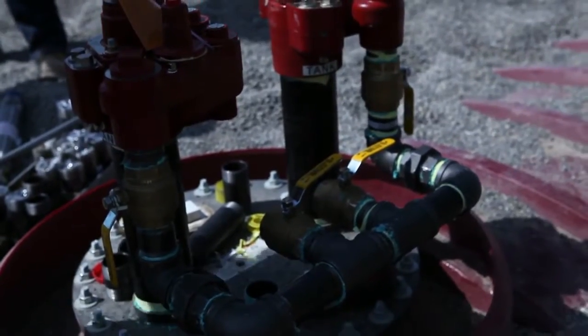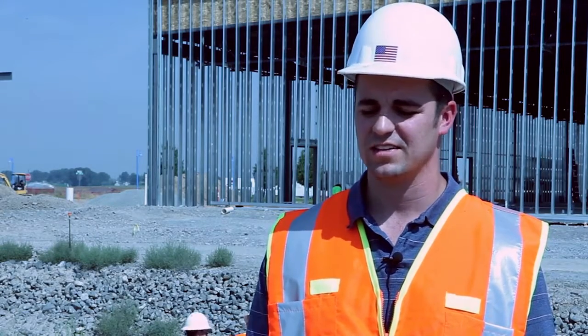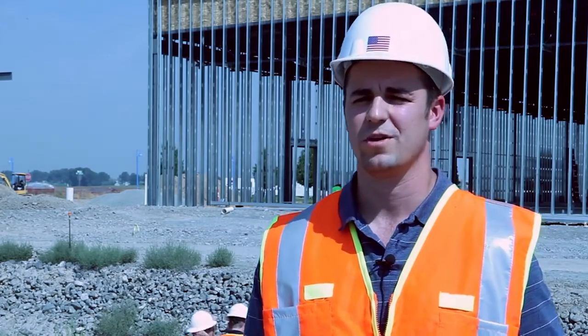When you manifold the pump configurations, if one pump dies you have the other one available. With one pump up you're not at optimal flow rates, but your site is still online. It'll hobble along during busy times, but during non-busy times you won't even notice it. The customer will still get 10 gallons per minute on the retail side or 60 gallons per minute on the commercial side with just one two-horsepower pump.